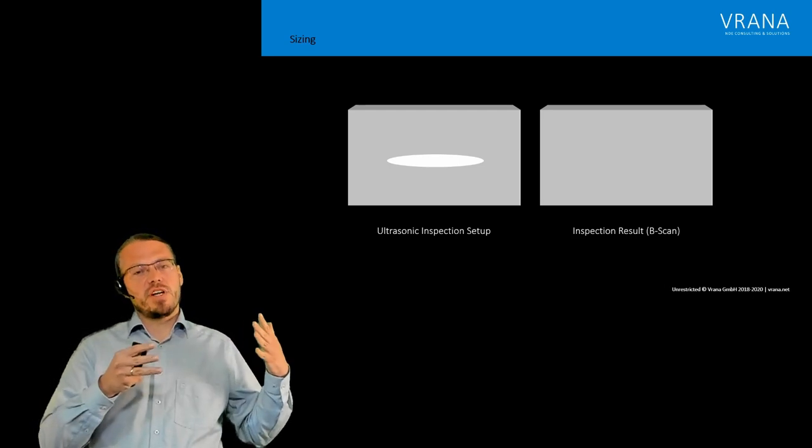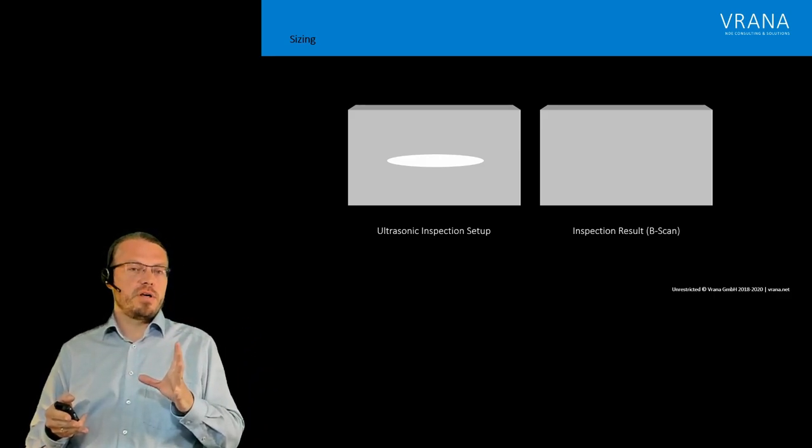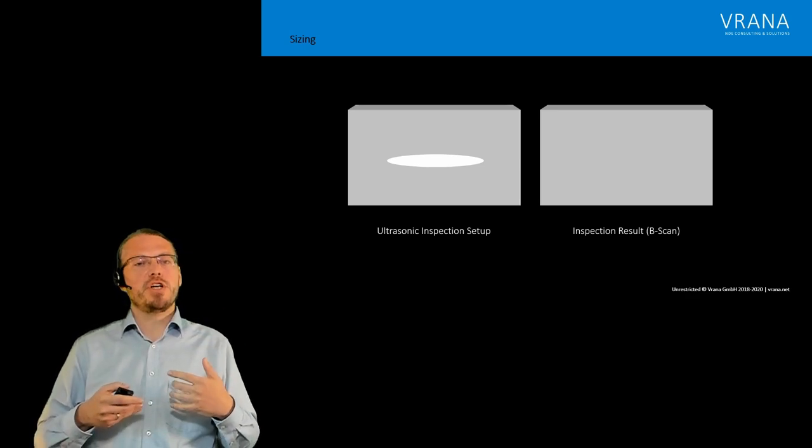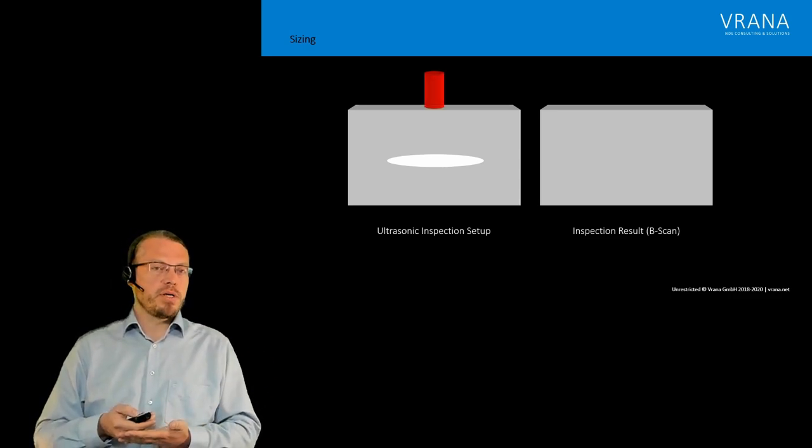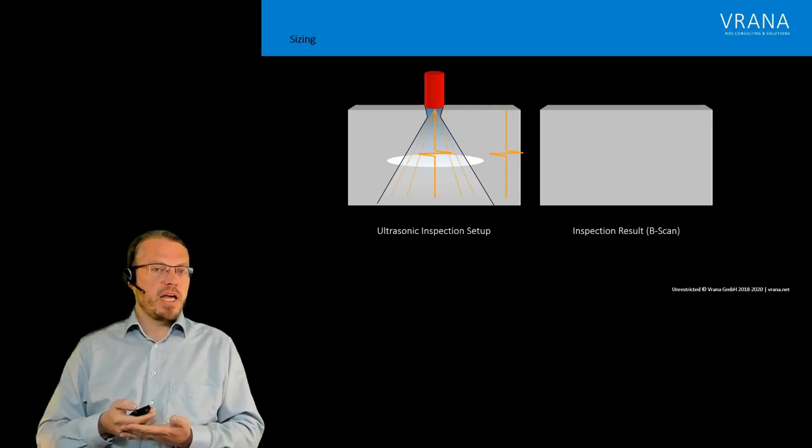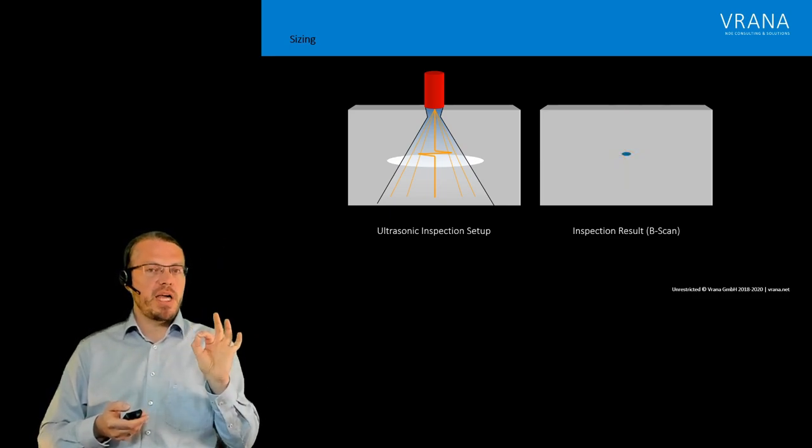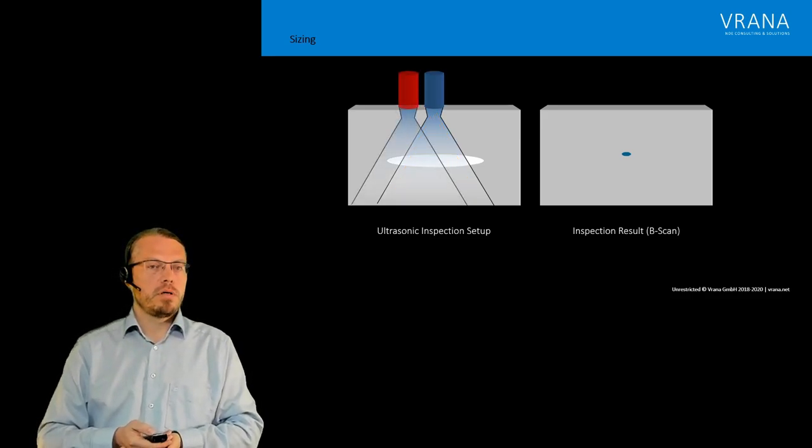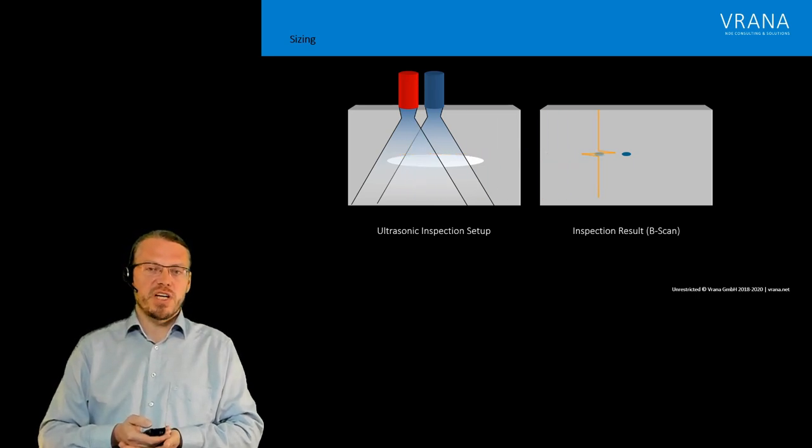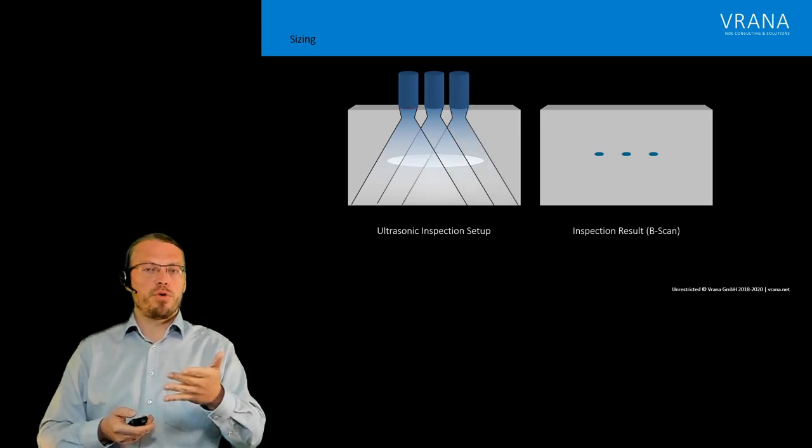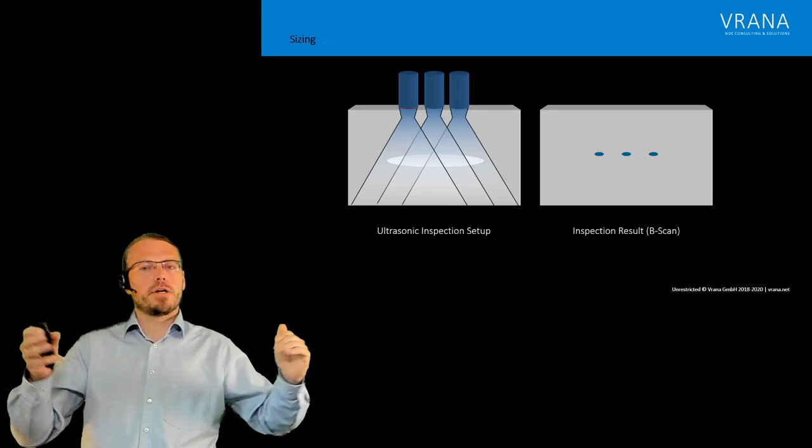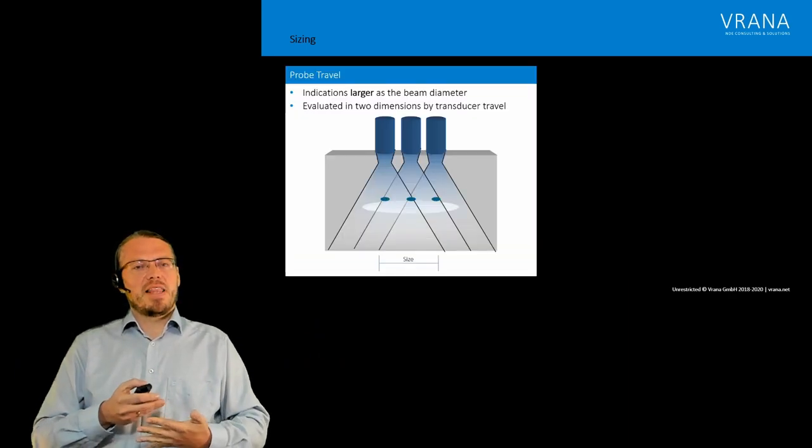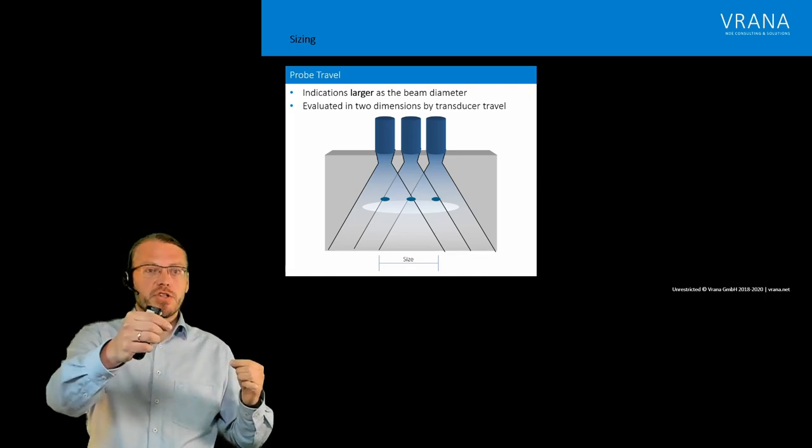Now finding an indication that's one thing. The other side is sizing those indications. And if we have, like in this example, a pretty large indication in that component. And we have our probe on our component. We start our ultrasonic pulse. We are getting back our signal. And then we are making a dot where we found our indications. That's that dot. Then we move our probe. We fire again. We get another signal. And we mark another dot. And we do that a third time for a third position. So then we can say okay that indication has length going from here to here. Now this can be done not only in one direction but also in the second direction.